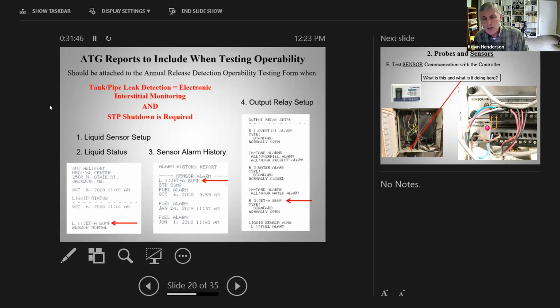So the simplest way to do that, of course, is to print these 3 reports again, actually 4. The status report we're always going to print, the sensor setup, the alarm history, but we're also going to add this output relay setup. So we'll look at the big long setup report. We're going to pull out this little part of it called the output relay setup and show that these alarms are connected to external relays, which are required by Veeder in order for you to be able to shut down the STP. You have to do that through an external relay.